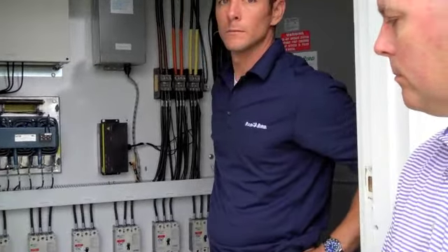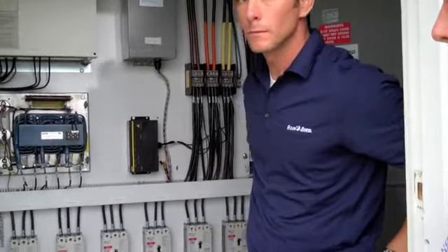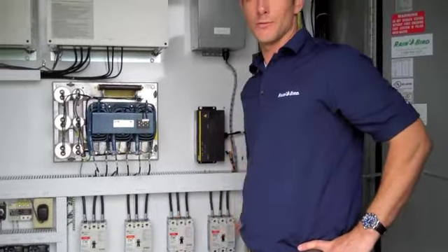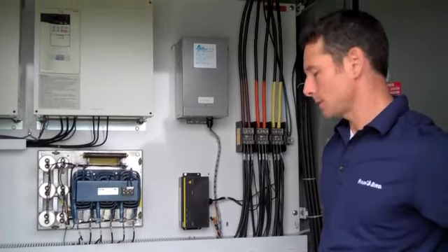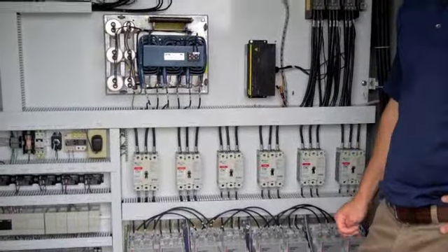What are the usual service issues with this, or parts that need to be replaced? In the older stations the big one was the fuses. In the last two days we've seen two custom-specced pump stations and both of them had one of the circuit breakers trip.